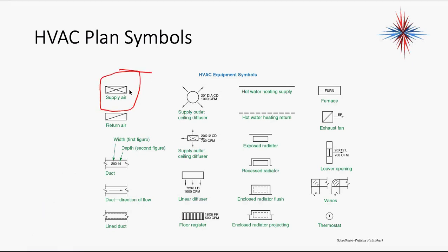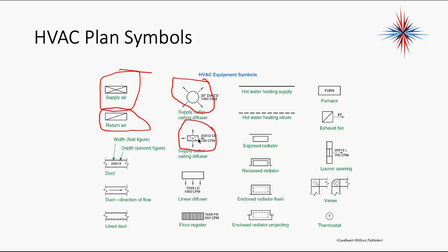The HVAC symbols you're going to use the most are supply air registers and return air registers. A supply air register is a rectangle with an X through it. A return air register is a rectangle with a single line across it. Those are the two you'll use more often. You'll also see a supply outlet — one of those circular things — where arrows indicate air goes in all directions, and a supply outlet ceiling diffuser works the same way.